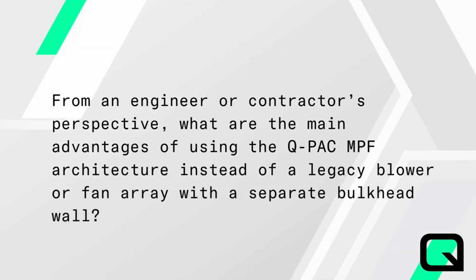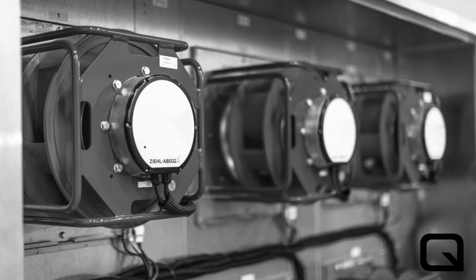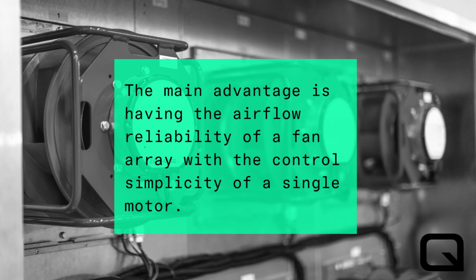From an engineer or contractor's perspective, what are the main advantages of using the Q-PAC MPF architecture instead of a legacy blower or fan array with a separate bulkhead wall? So when it comes to Q-PAC's MPF, the main advantage is having the airflow reliability of a fan array with the control simplicity of a single motor. We've designed our product to operate like a single device with a single point of connection. So that's one 0 to 10 speed signal, but without drawbacks of complex arrays.